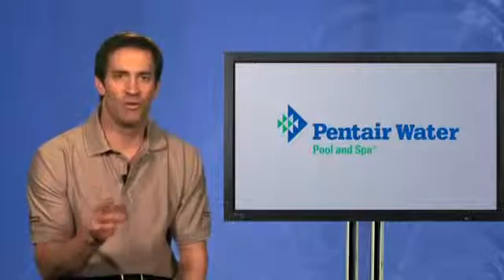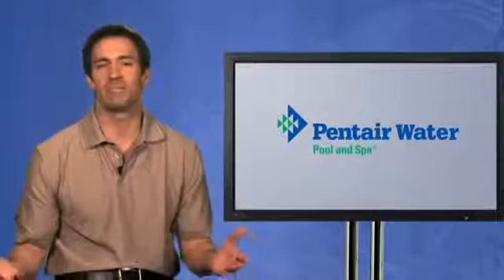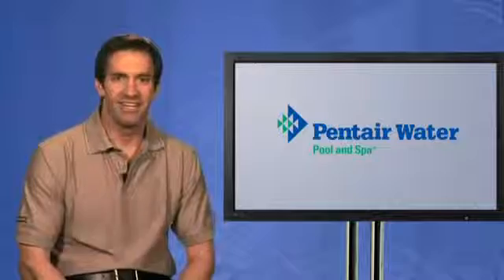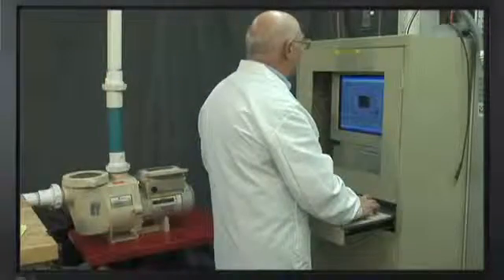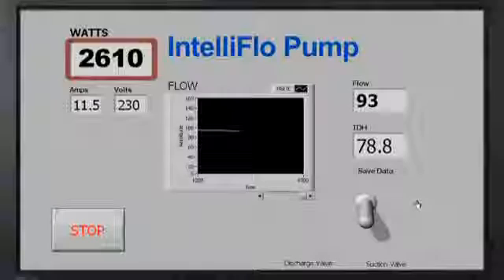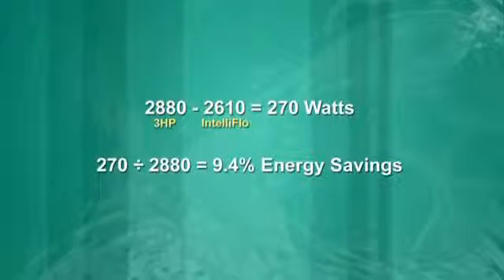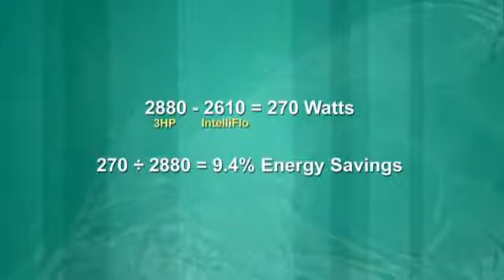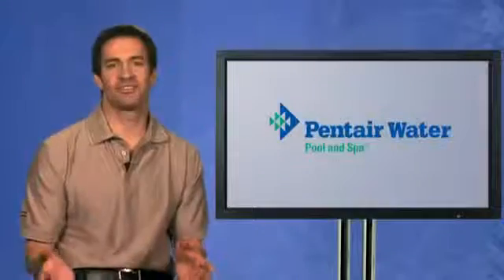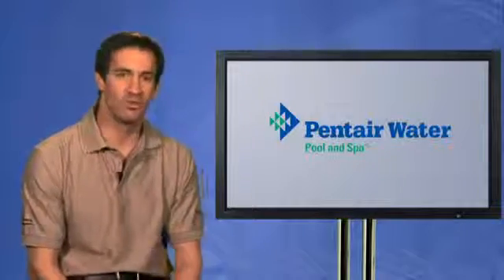Also remember that comparing one of the new variable pumps to a three-horsepower pump applies to less than five percent of all pumps installed. In fact, in some states like California, three-horsepower pumps are banned for use as a residential filter pump. But for argument's sake, let's see what happens when you run an IntelliFlo pump flat out and measure how many watts it uses compared to a three-horsepower pump at the same performance. The variable drive technology consumes 9.4 percent fewer watts than the single-speed pump. Also consider that you simply would not set a variable drive pump at its maximum speed to accomplish most water-moving tasks.